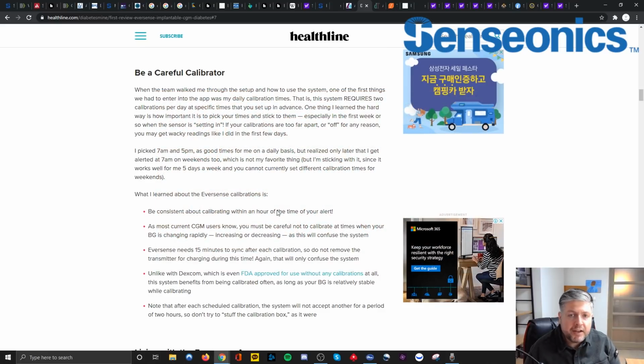You do have to calibrate the Senseonics product twice a day with finger pricks, whereas you do not have to calibrate the Dexcom or the Abbott products. But the flip side is that the Dexcom, the Abbott, and the Medtronic products are all anchored into the skin with a needle, and it restricts the patient's range of motion and they feel the skin pulling. Whereas the implant from Senseonics is not going to have those issues. So it's like a trade-off. With Senseonics, you have to deal with the 2 finger pricks a day, but you don't have the constant pulling of the skin-anchored product.